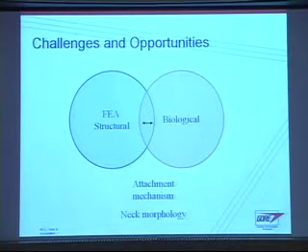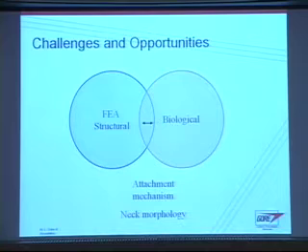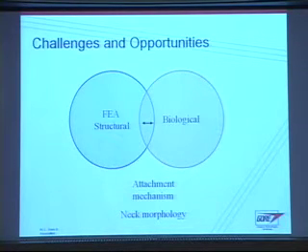To attack these failure modes, we're looking at this from two different perspectives. The first is from an FEA structural perspective, as well as these biological markers which have been discussed over the last two days. Combining the two, we look at the attachment mechanism as well as the effect on neck morphology — whether you're going to impose neck dilation by your attachment mechanism, or whether putting a device in an already angulated neck is going to increase the propensity of some sort of device failure.